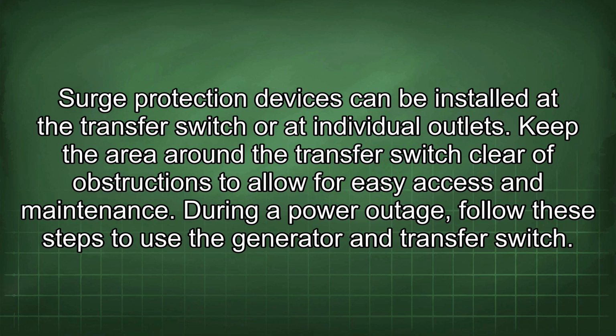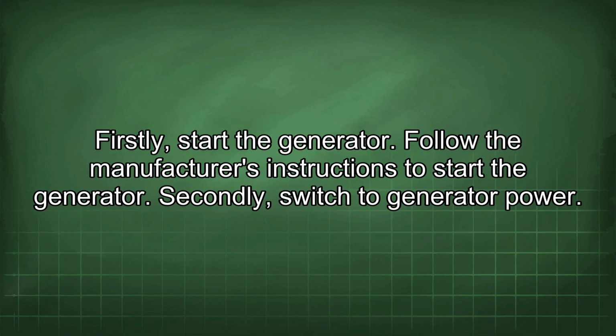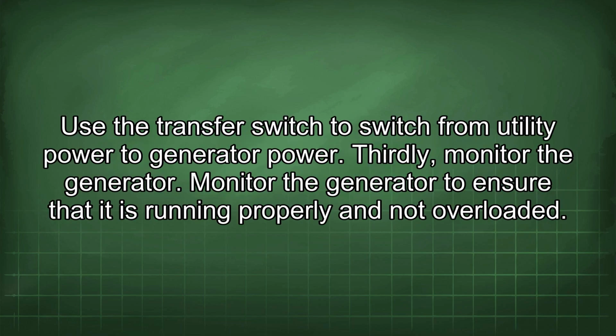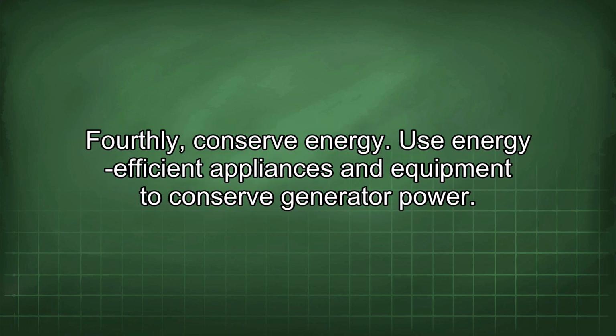During a power outage, follow these steps to use the generator and transfer switch. Firstly, start the generator. Follow the manufacturer's instructions to start the generator. Secondly, switch to generator power. Use the transfer switch to switch from utility power to generator power. Thirdly, monitor the generator. Monitor the generator to ensure that it is running properly and not overloaded. Fourthly, conserve energy. Use energy-efficient appliances and equipment to conserve generator power.